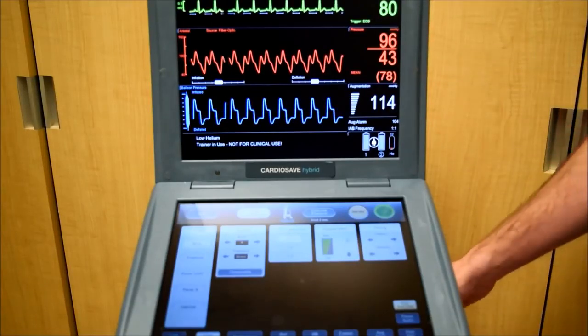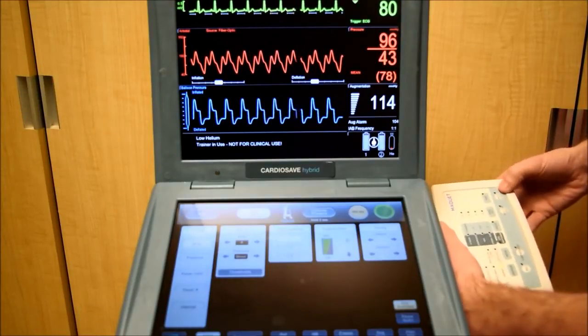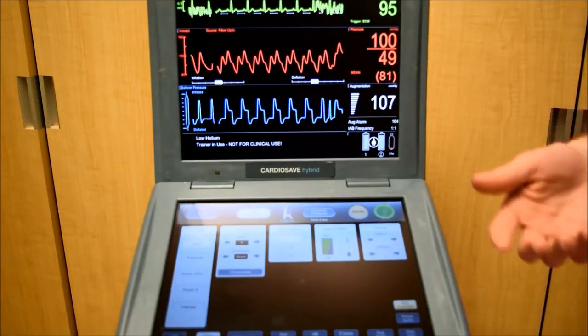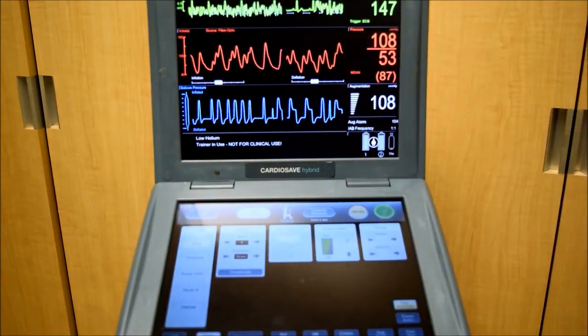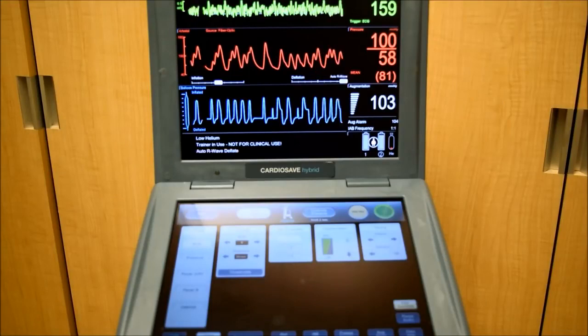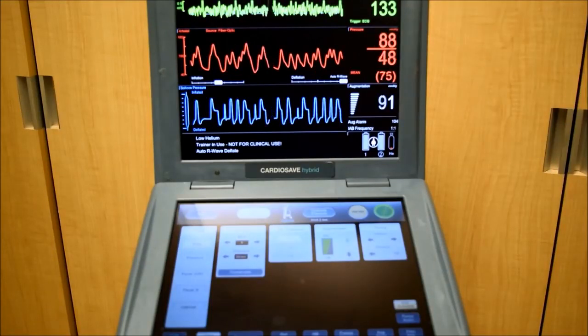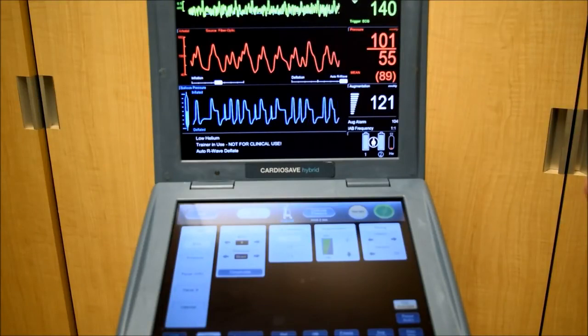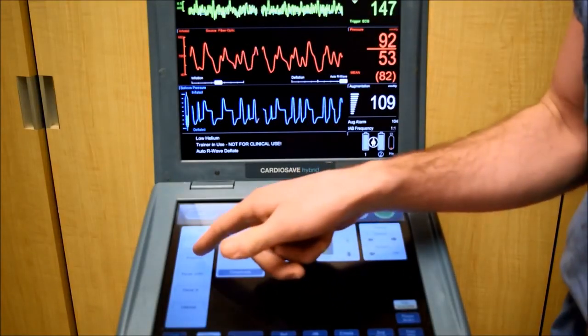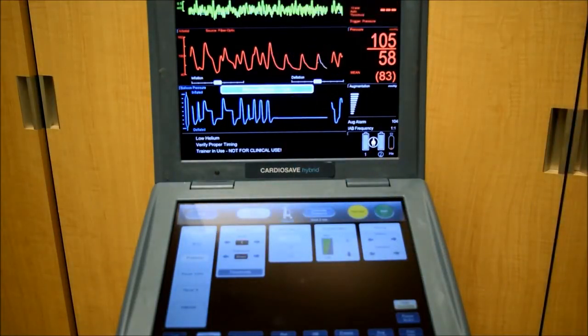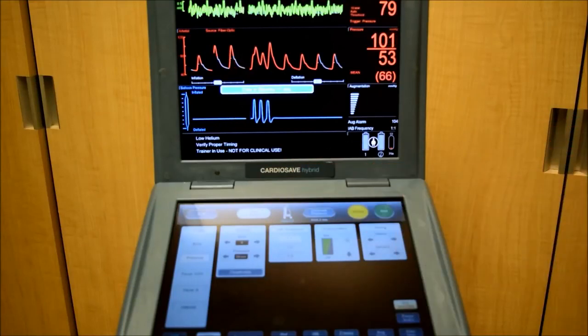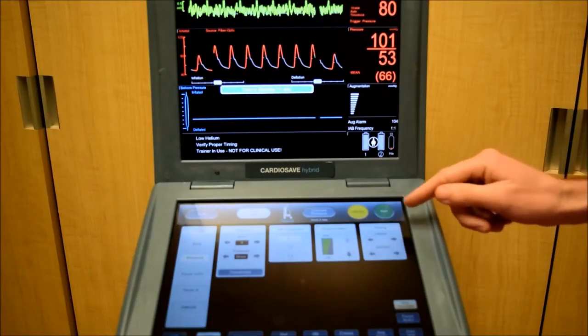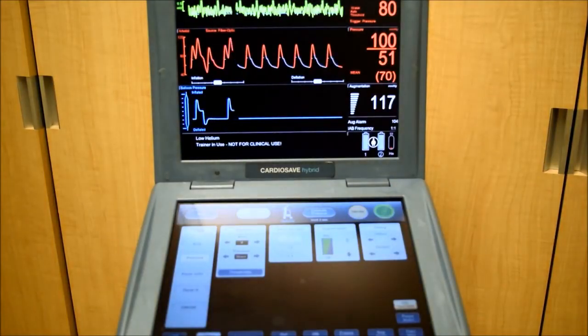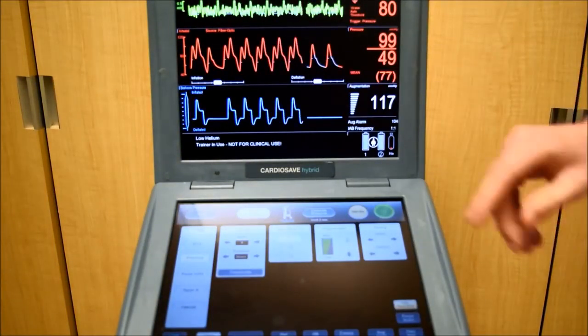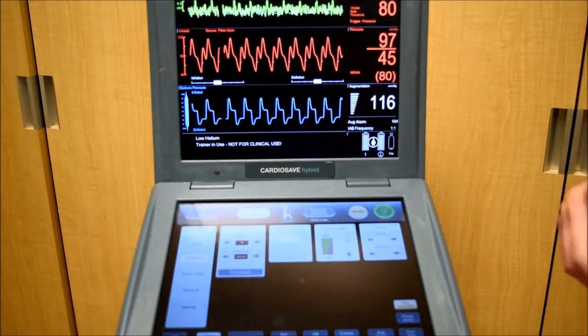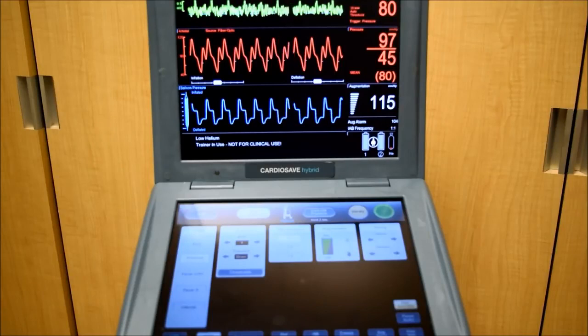However, if you're in the operating room and you get electrical interference like this, you'll no longer be able to use ECG. You'll notice the balloon is sporadically beating and it has no rhythm to it because its trigger source doesn't allow for it. You can adjust this by using pressure as your trigger. After you switch the trigger, the balloon is automatically put on standby, so you'll have to start it again. You'll notice, even though we don't have a normal ECG rhythm, our balloon is beating appropriately.